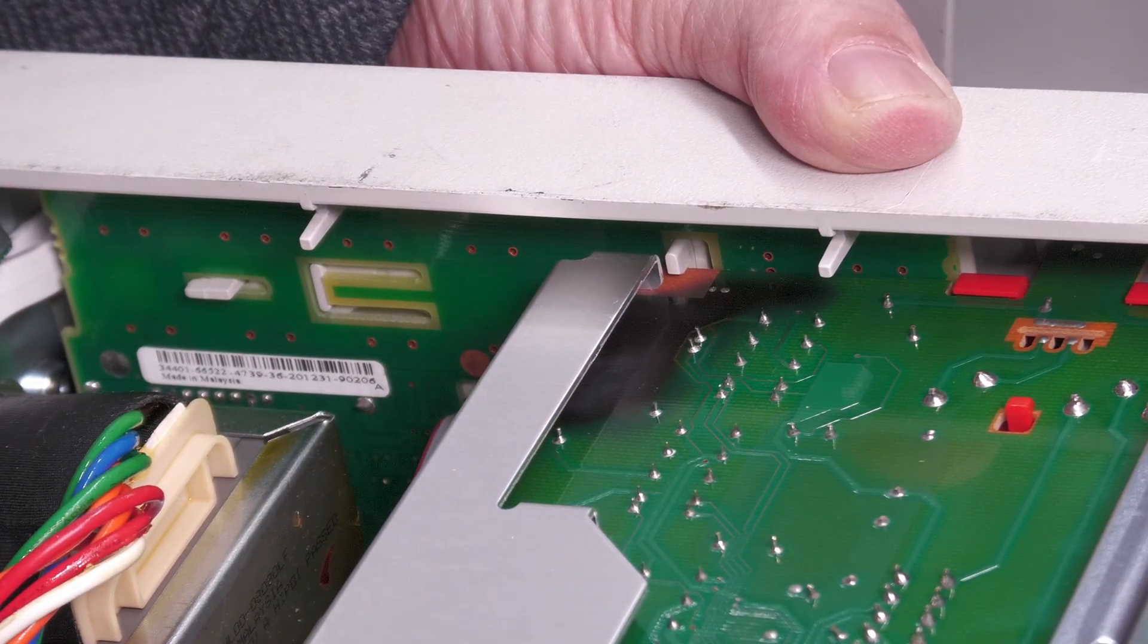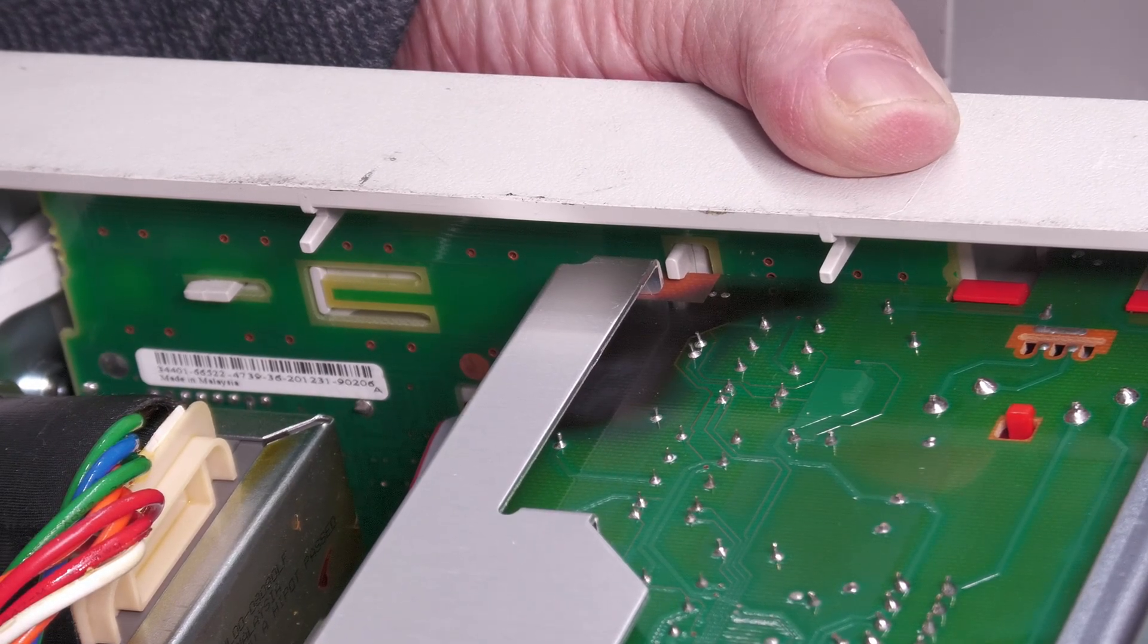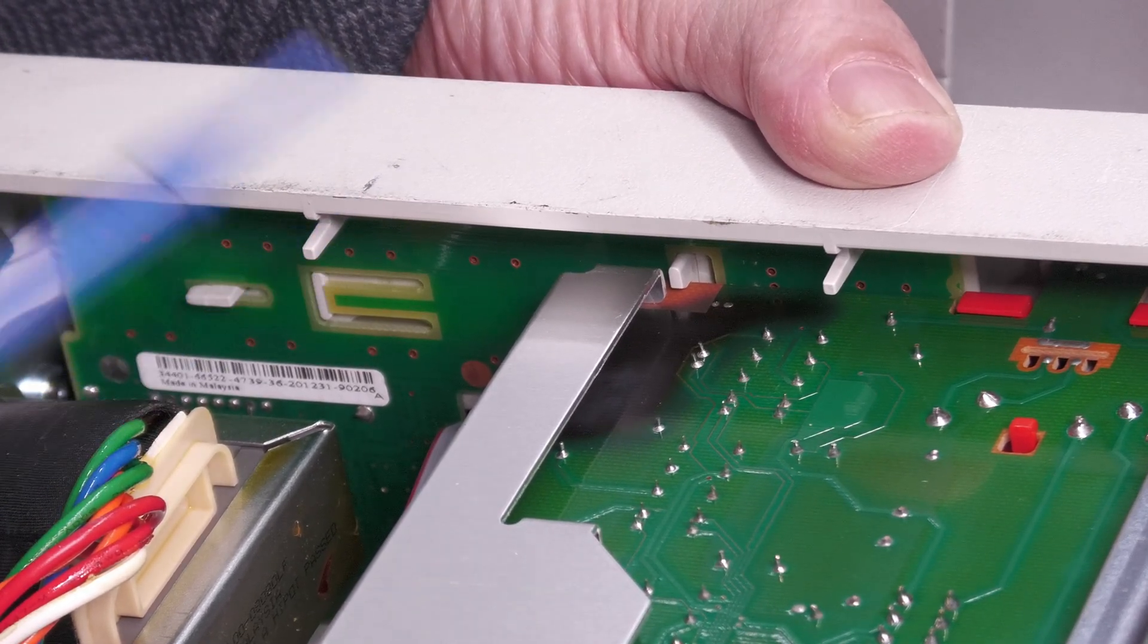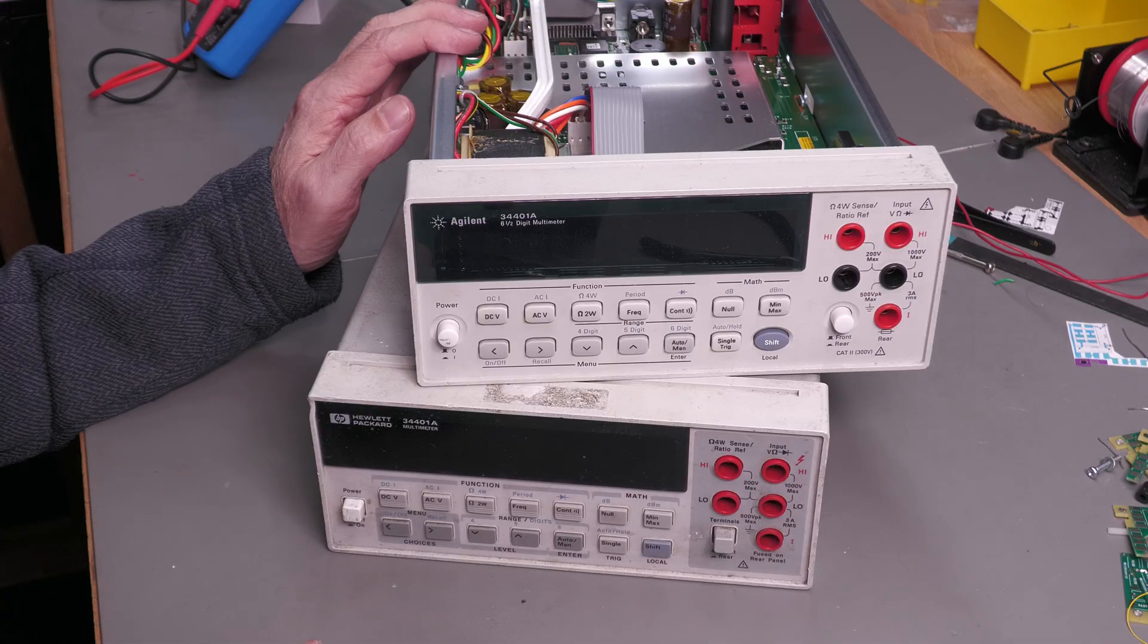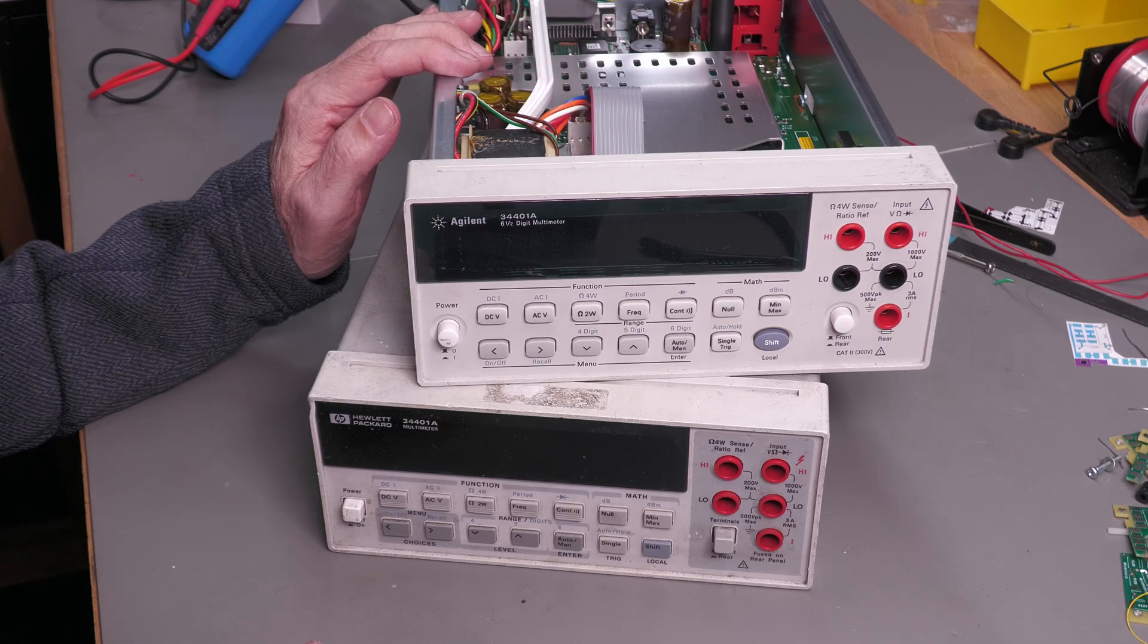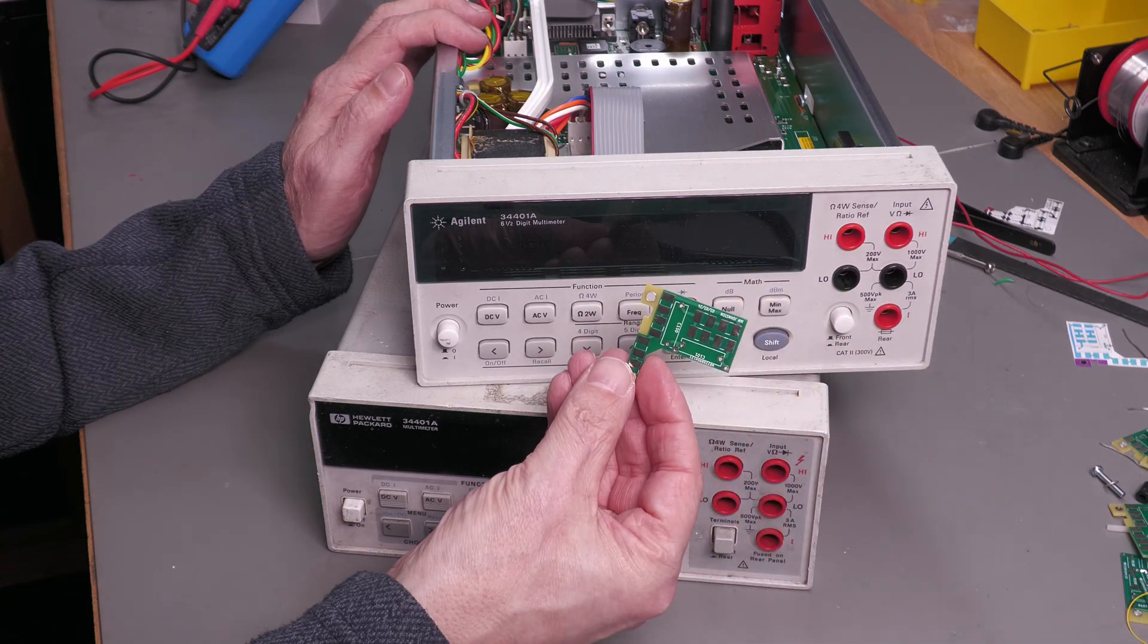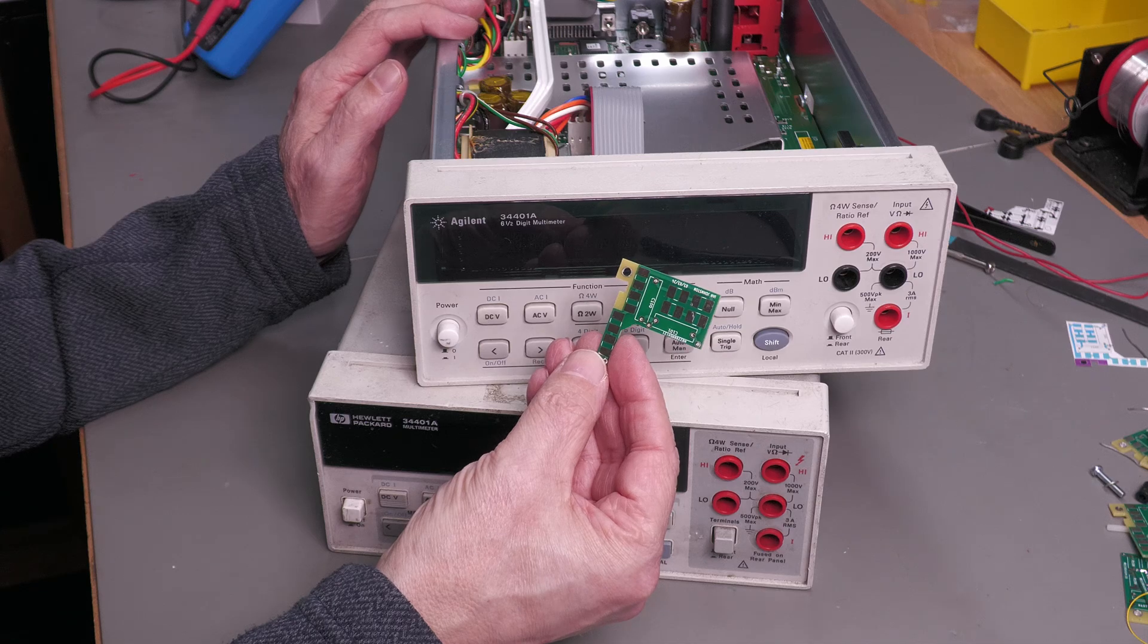Exactly the same fault. Well, not too surprising. These two 34401As came from the same place. So I wonder if the technician blew one of them up and then proceeded to blow the other one up as well. Wow. So I've got an identical fault with this second unit here. But I'm going to repair that one off camera. It's obviously going to be the identical process to what I did with the first unit. And luckily enough, I've got quite a number of these boards here and the components to go on them. So it should be a quick and easy repair as well.